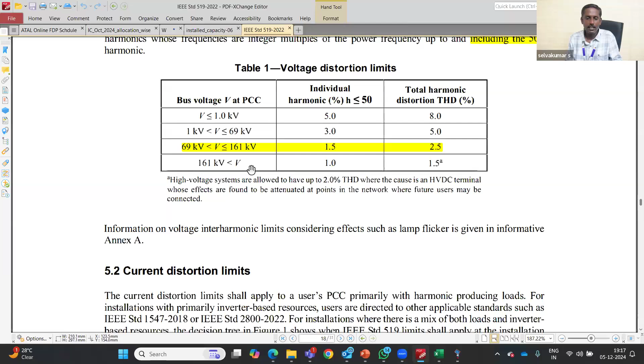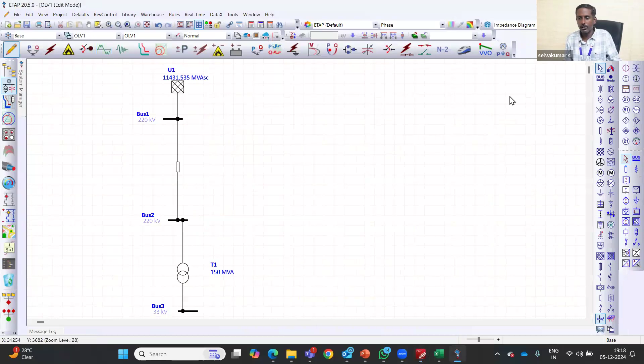Like we have 136% THD here, versus the acceptable limit at 220 kV, which is 1 to 1.5 percent. But we have 136 percent, which is not really a system to have. So we also need to find out what mitigation measures we need to take.